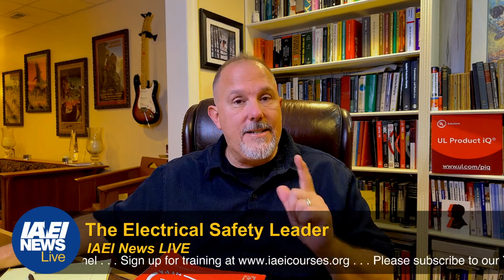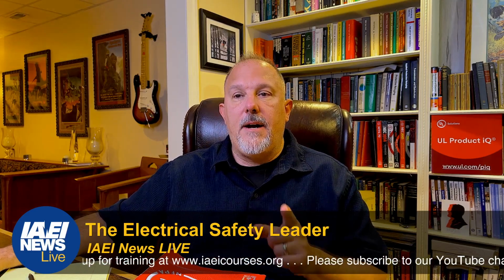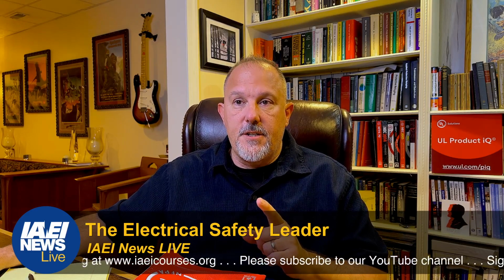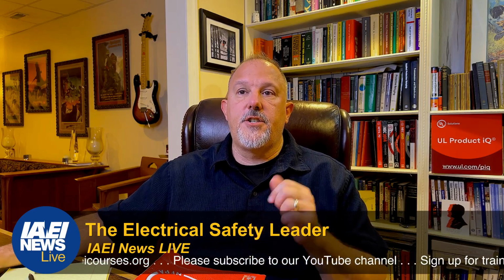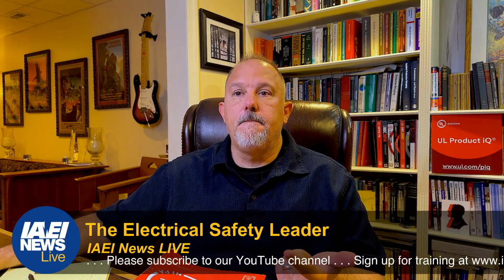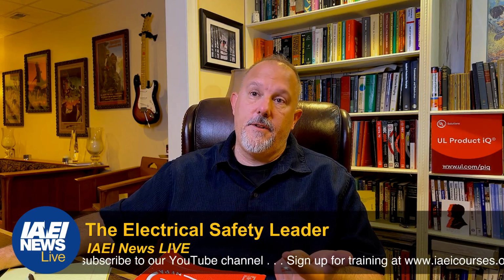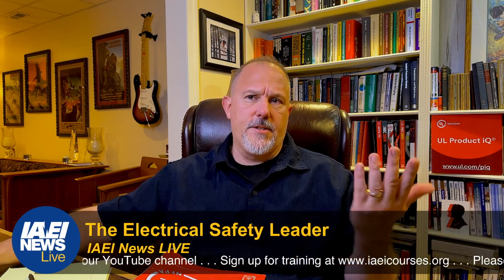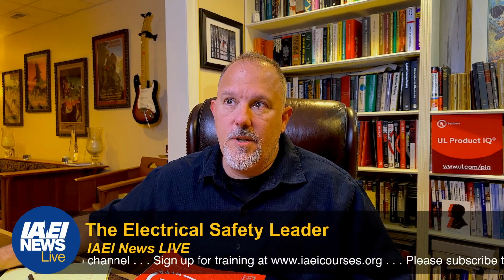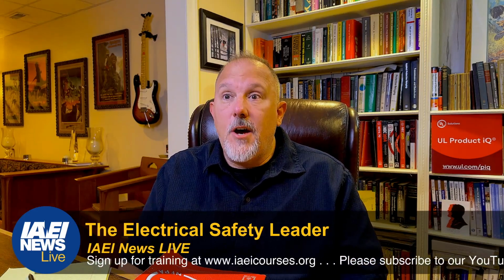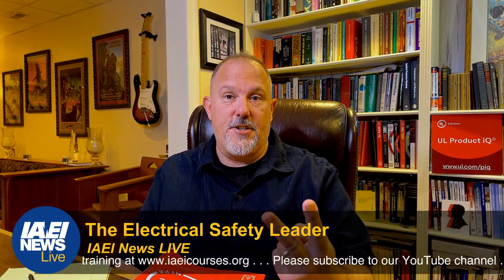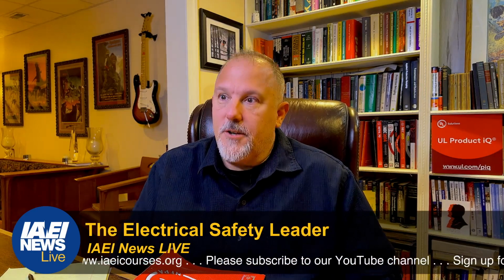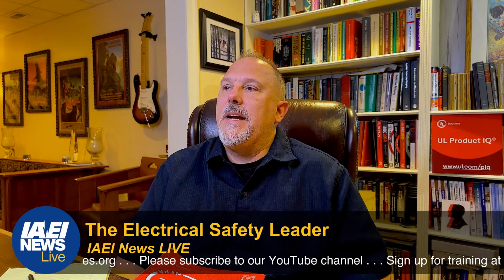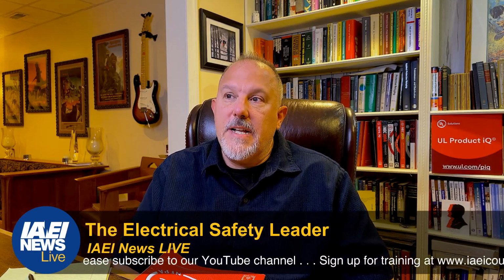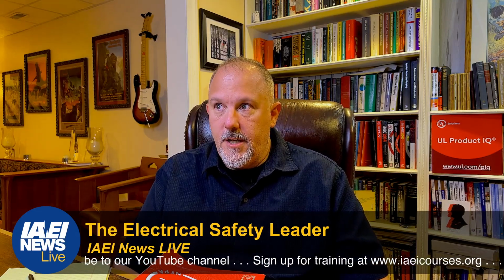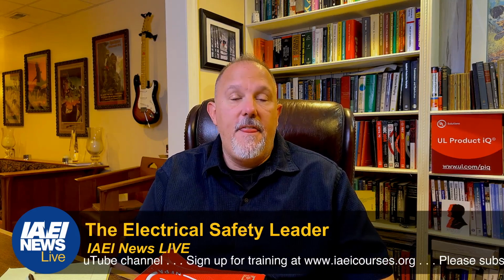Article 100. Let's talk definition. If you go to the numerous definitions and terms that are defined, you'll see surge arrestor, surge protective device, and those are the two surges. I thought there were three. I don't know why. It's suspended ceiling and support areas. So let's talk surge arrestor first. What's a surge arrestor? A surge arrestor is not a surge protective device. How do we know that? Because we have two different definitions. Duh, right? A surge arrestor is a protective device for limiting surge voltages by discharging or bypassing surge current. It also prevents continued flow of follow current while remaining capable of repeating these functions. That is a surge arrestor.